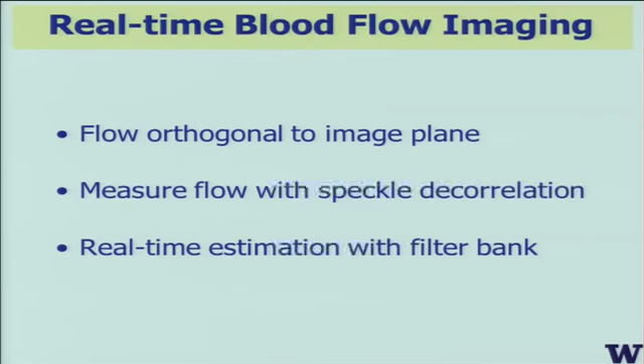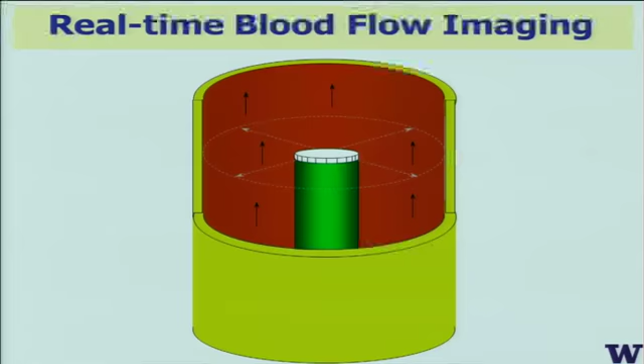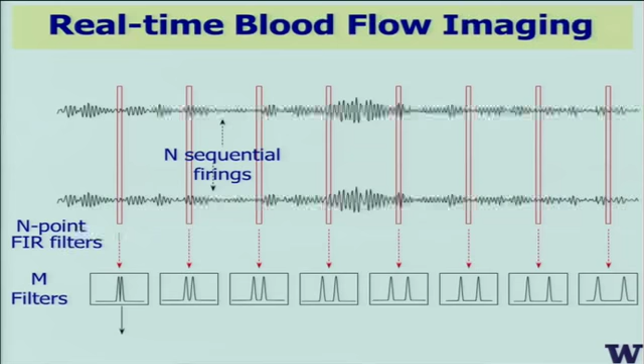Can a mechanical scanner do any of this? No, because it's physically moving while the blood is flowing. So when you see a relative motion, you don't know whether it's a transducer wobble, a slight imperfection in the transducer wobble, or a blood flow. Here, it's all done electronically because you have the array. So here's that geometry. You have an array which is side-looking and the blood flowing this way. But there are standard signal processing tricks that you can do using filter banks and decorrelation processing to notice the changes and actually quantify the changes in blood flow.